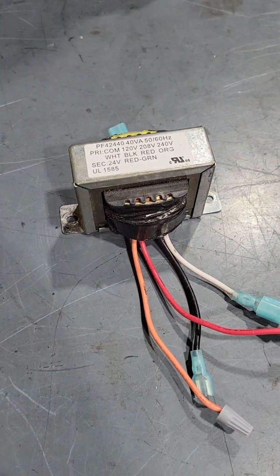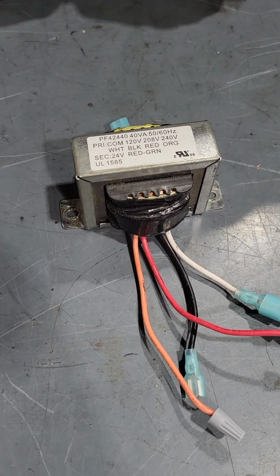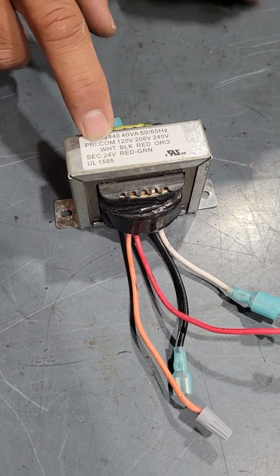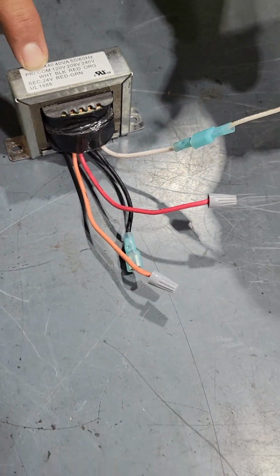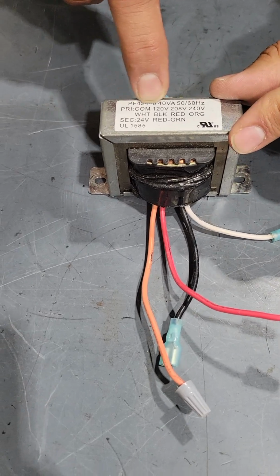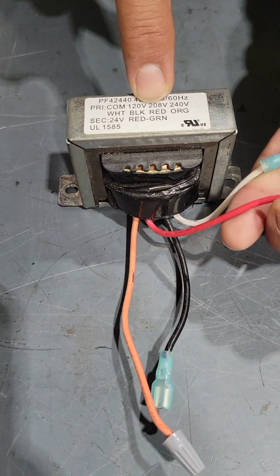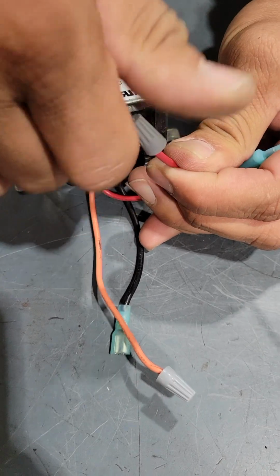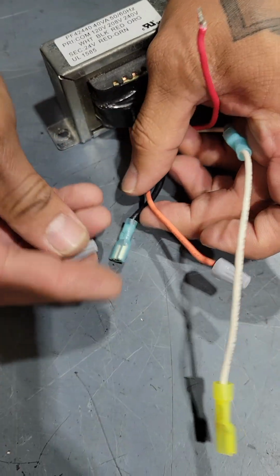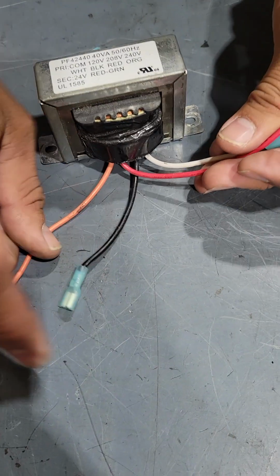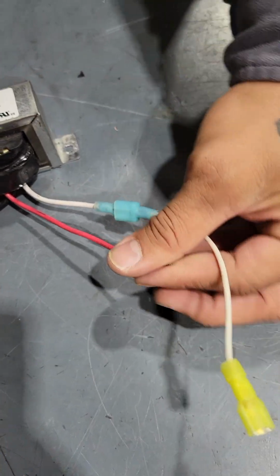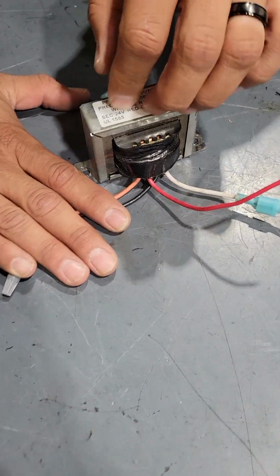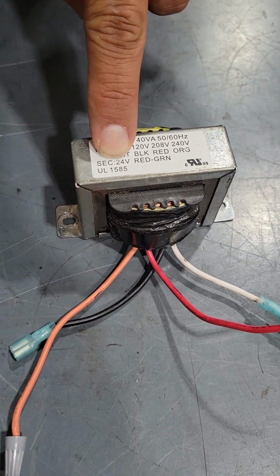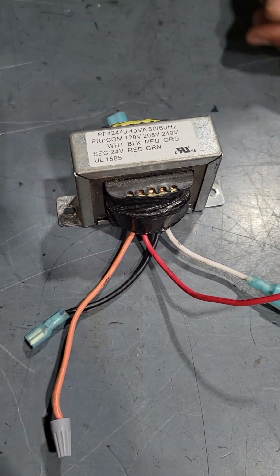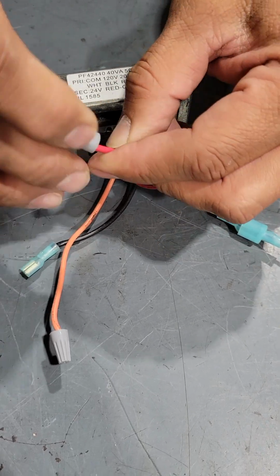So in this case, we have 208 volts in our shop. So the two wires that we would use would be your common, because every AC circuit needs a common wire, plus your line voltage wire. So if we're doing 208, we'd be hooking up these two, red and white, and we'd be capping off black and orange, because we wouldn't use those. Those would be out. These would be hooked up to your system, producing secondary voltage of 24 volts. Okay, that's a step down transformer.